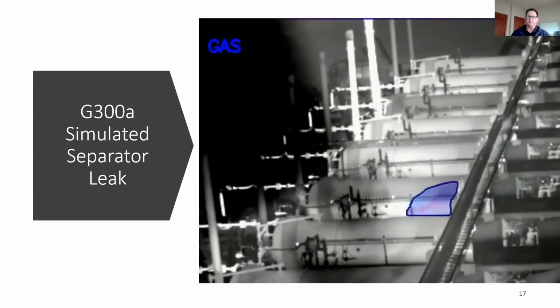I'll try to keep this as simple as possible. In that Alara camera that we're using for the tank levels, it's a long wave camera, covering a broad spectrum from about 8 microns up to about 14. In this gas detection camera, we're in the mid wave, between 2 and 8, and we're filtering it even deeper.